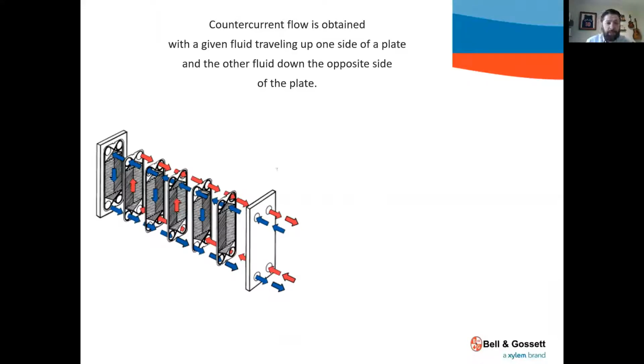proper alignment. So what you see here with the hot and the cold, you see that one is going on the bottom, the other on the top. That's counter current flow. The heat exchanger is equal on both sides, so I could switch the hot and the cold. You could switch the sides, but as long as you maintain the counter flow, meaning one's coming in the bottom, the other the top. And as you can see, this scrubs and gets the most transfer on those plates. You see going up and down either side, the hot and the cold water. That's where the transfer occurs, guys.